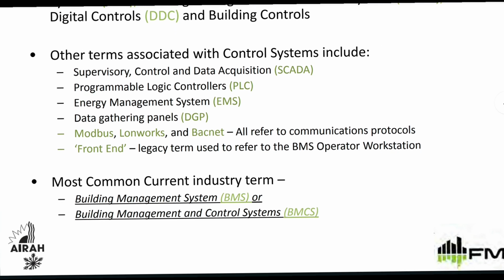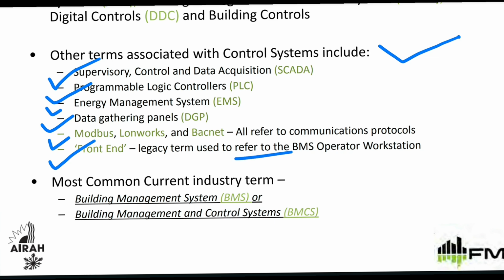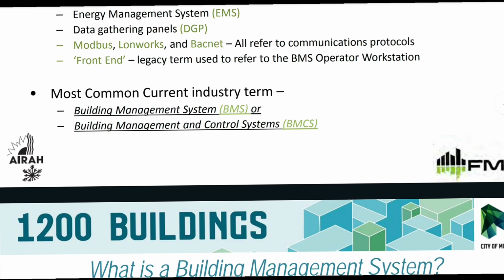Other terms associated with control systems include SCADA, supervisory control and data acquisition. Second is PLC, programmable logic controllers. Third is EMS, energy management system. Fourth is data gathering panels, DGP. Next are Modbus, LonWorks and BACnet, which all refer to communications protocols. Next is front end, a term used to refer to the BMS operator workstation. The most common current industry terms are building management system, BMS, and building management and control system, BMCS.